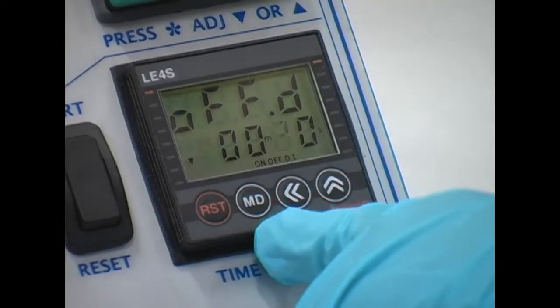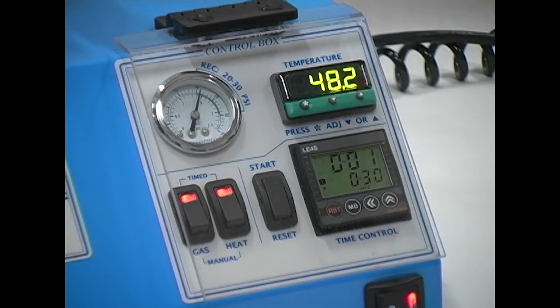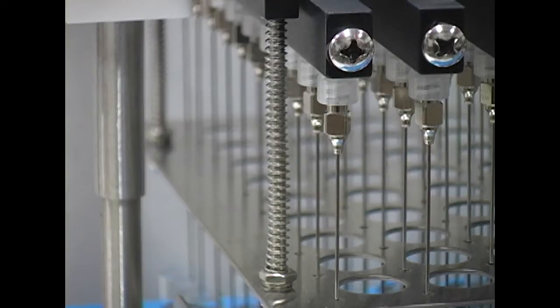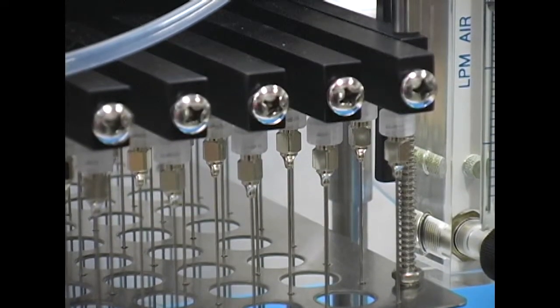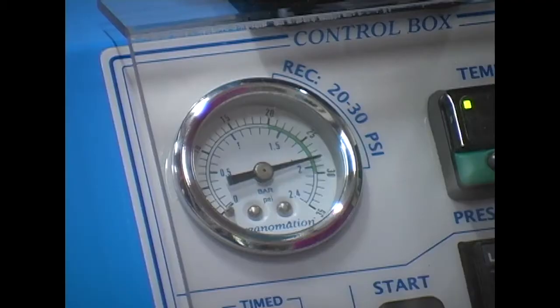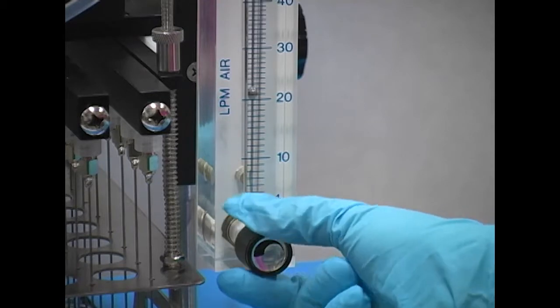The built-in timer allows the user to easily shut off the heat and nitrogen gas once the evaporation is complete. Nitrogen gas is delivered to samples through individual stainless steel needles connected to the hand-built gas distribution manifold. The gas is controlled with the internally installed pressure-reducing gas regulator and adjustable flow meter.